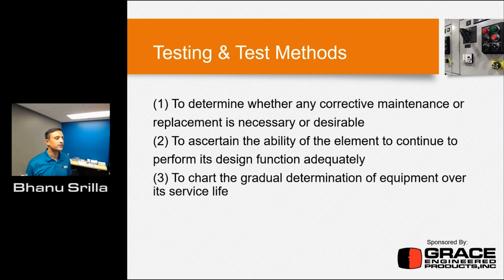Tests and test methods determine whether any corrective maintenance or replacement is necessary or desirable. So whenever you do any testing, you're understanding whether any corrective action is required, right? With a thermography program, or checking the tightness of bolts and nuts, you need to make sure you decide what kind of corrective action needs to be taken, not just monitoring or testing. This is to ascertain the ability of the element to continue performing its design function adequately, and to make sure your system is producing the same test values as it's supposed to be giving out.